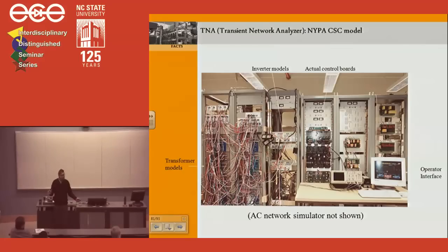On this simulator, we have the actual controls that are at site. This was a test bed, so it simulates everything, including the magnetizing current of the transformers. This was our test bed that we played around with to develop our controls, to test the system under faults, to convince the utility that, look, these are the results. And when we didn't understand anything at site, we would try to reproduce it on this thing so that we could understand it.